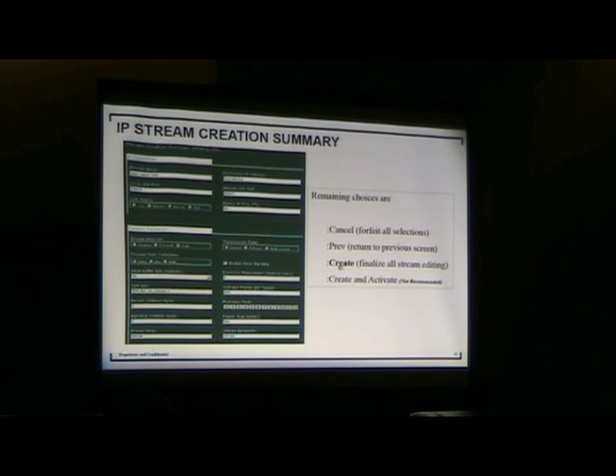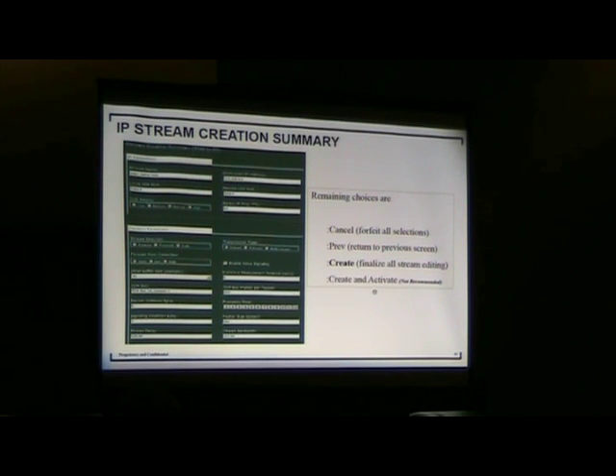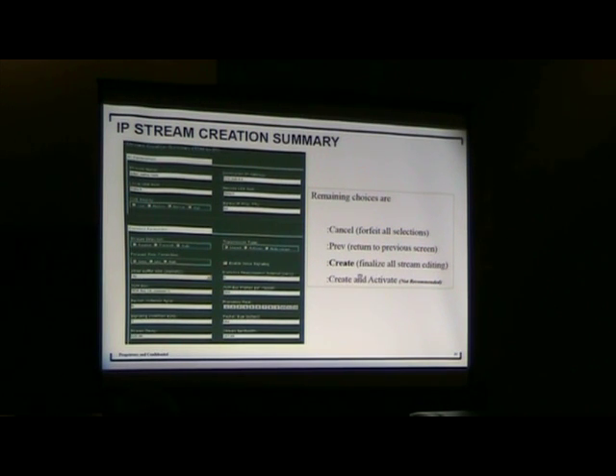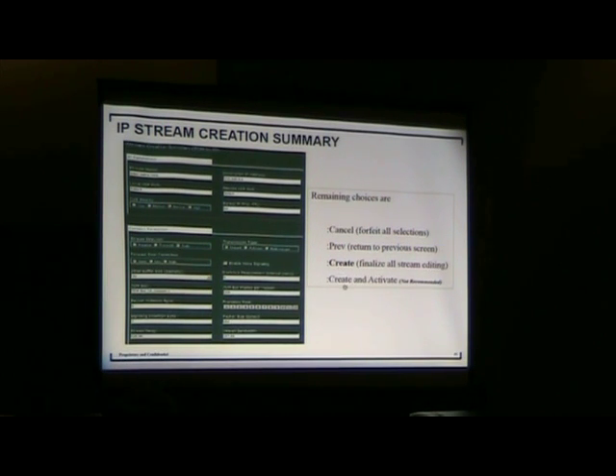Once you establish the values through the walkthrough, you have four choices at the bottom. Use the Create button instead of Create and Activate — if you create and activate and there's a parameter conflicting with an active stream, the stream will not activate and also will not create, and you've lost your details. By pressing Create, it will always let you create duplicates of existing streams without running them on the bus, so you can edit them after the fact and then activate them individually to see which ones fail.